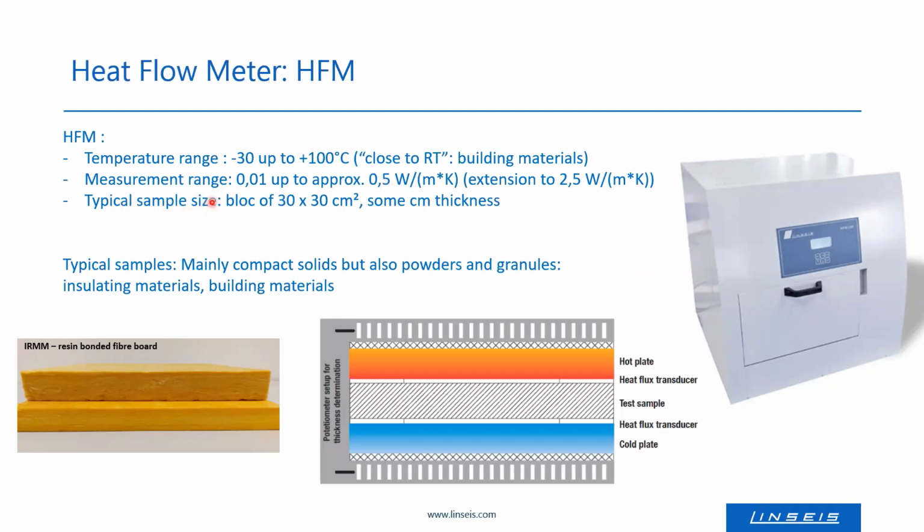Typical samples are blocks, or like shown here for this insulation material, of a size of 30 by 30 centimeter with a couple of centimeter thickness. And they are positioned here behind this door between the hot and the cold plate.